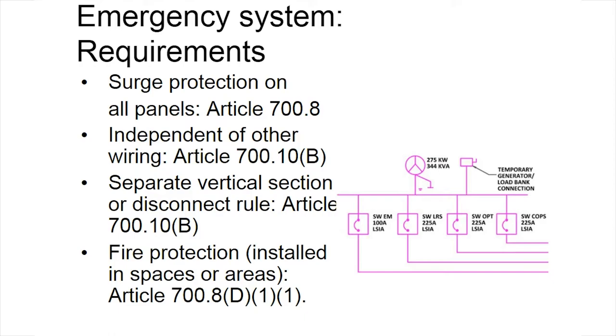And Article 700.8(D)(1)(1) requires some form of fire protection for the emergency system in certain occupancies, in particular 1,000-person assembly occupancies, high-rise buildings with certain occupancy types, specifically hospitals, and educational buildings with more than 300 occupants. Fire protection can be a listed system. It can be a fire barrier. It can be concrete encasement or a fire suppression system.